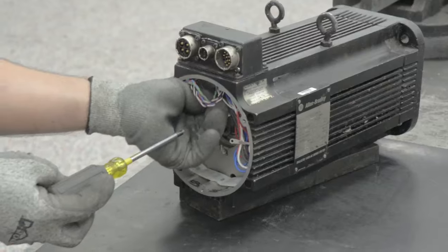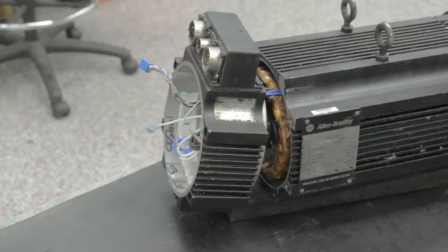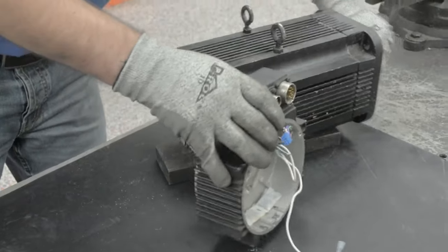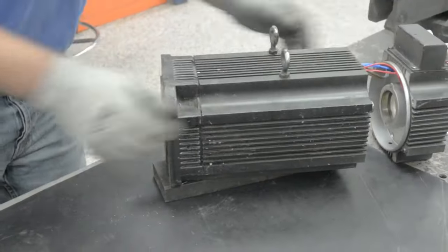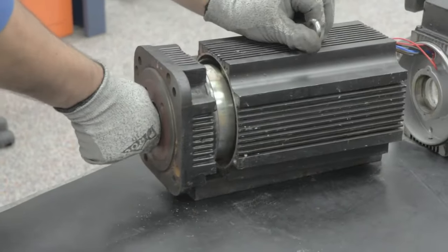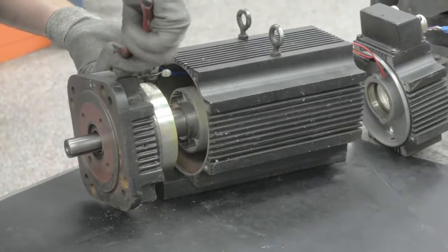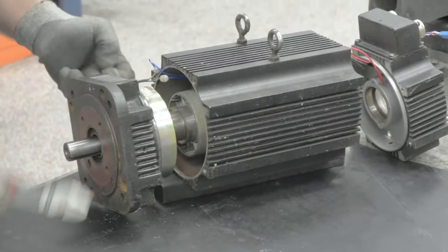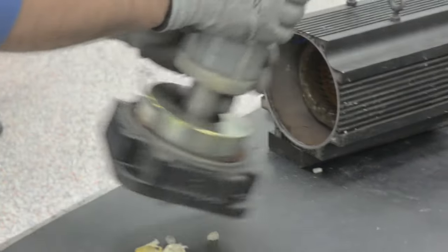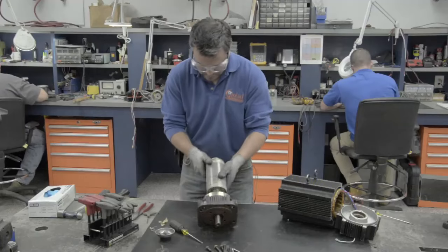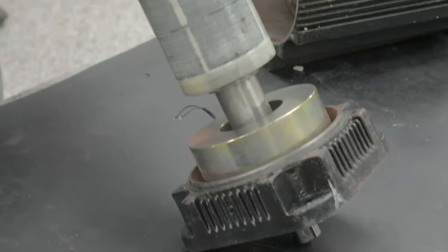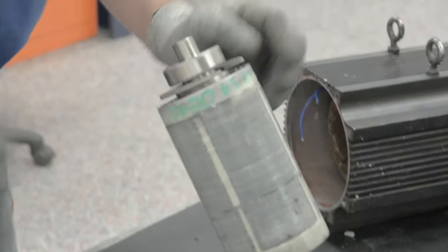Next, we will remove the end bell and take the encoder down the hall to be repaired on the industrial electronic side. Then we'll clean the motor and dry it. Now we are removing the front end bell. Here we'll disconnect the brake and remove it from the stator. We have to inspect the rotor and the shaft.